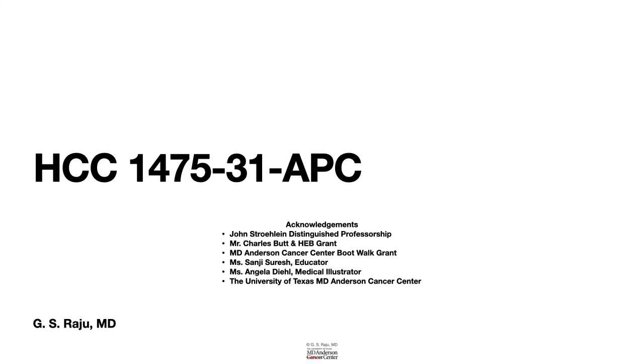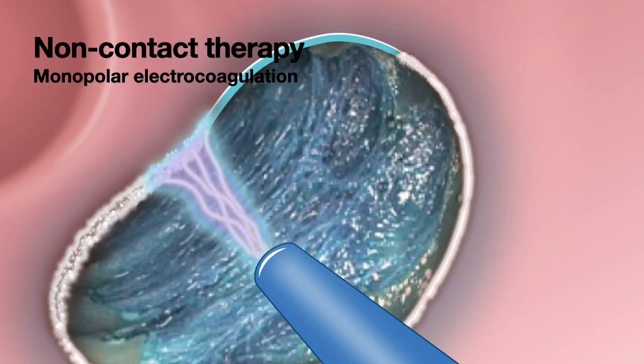Greetings. Let us learn about APC, otherwise known as Argon Plasma Coagulation. This is a monopolar electrocoagulation and it is a non-contact thermal coagulation therapy. It is non-contact because the argon gas forms the plasma that allows the electrical current to travel along the gas and create coagulation.